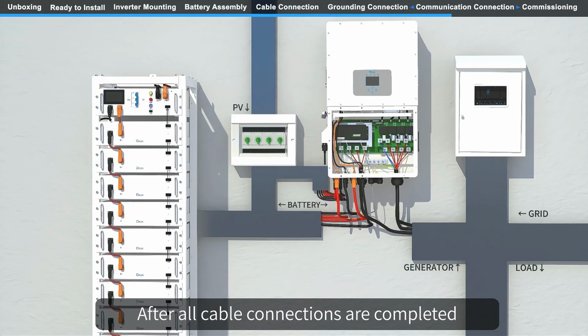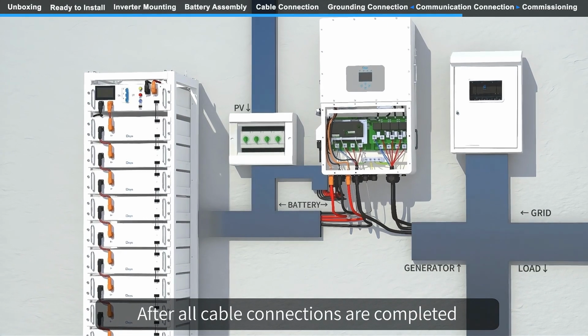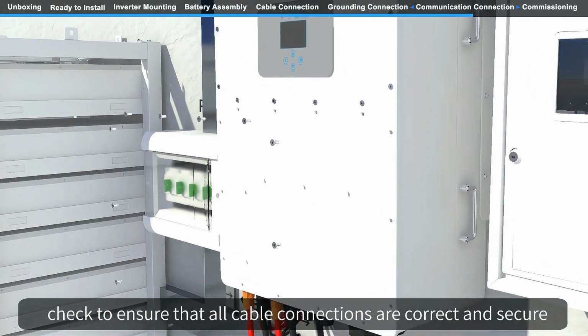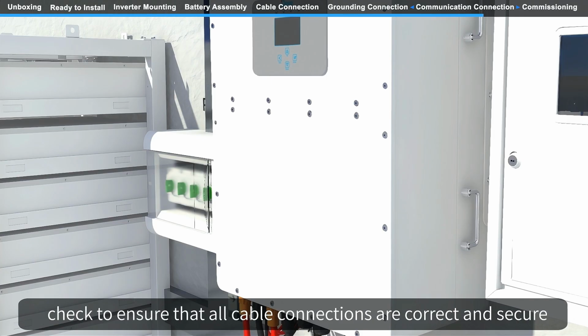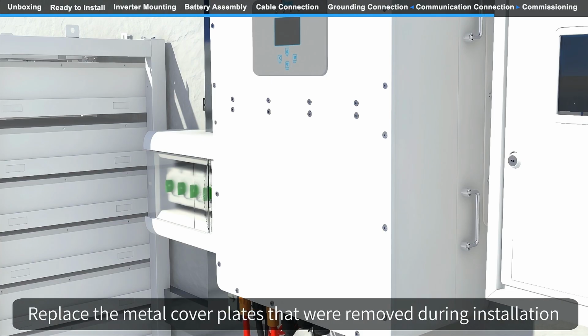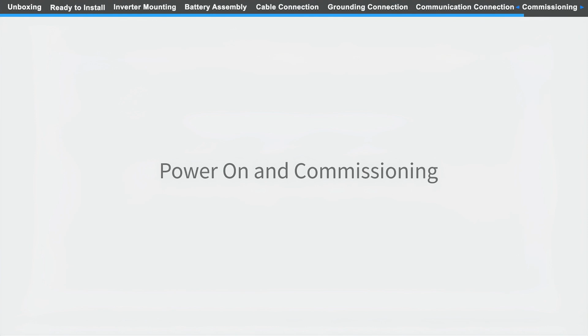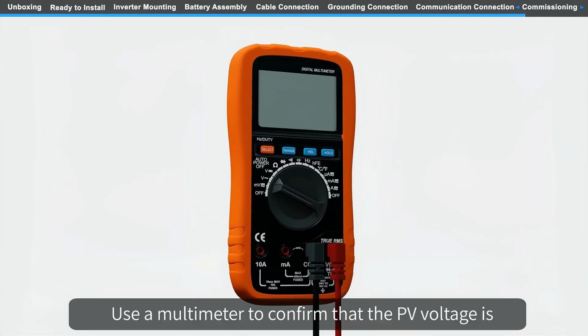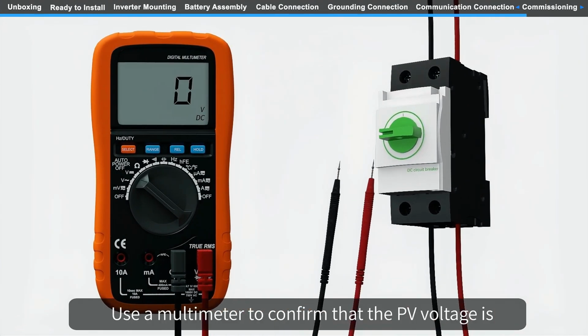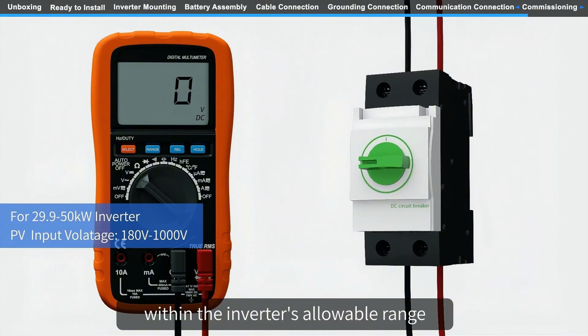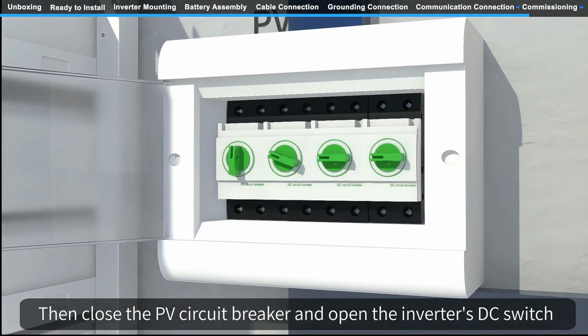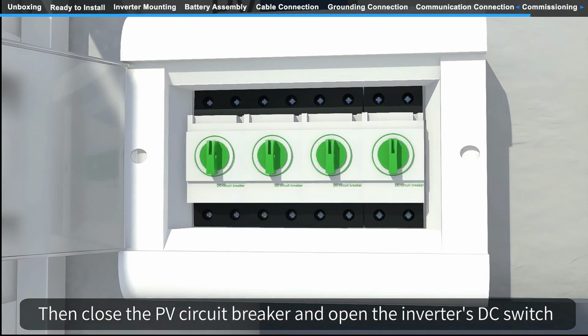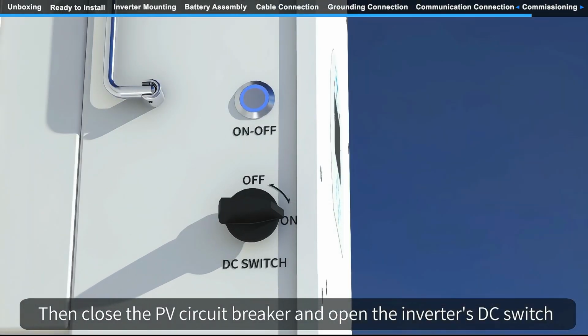Complete installation. After all cable connections are completed, check to ensure that all cable connections are correct and secure. Replace the metal cover plates that were removed during installation. Power on and commissioning. Use a multimeter to confirm that the PV voltage is within the inverter's allowable range. Then close the PV circuit breaker and open the inverter's DC switch.